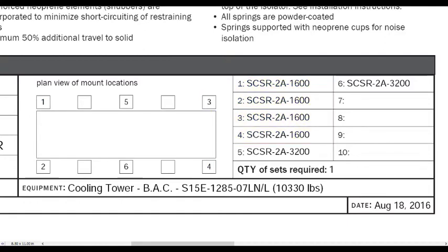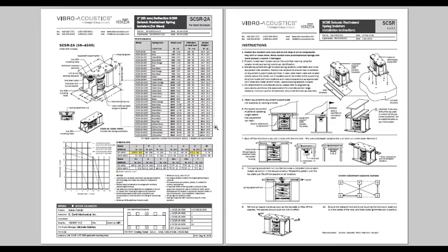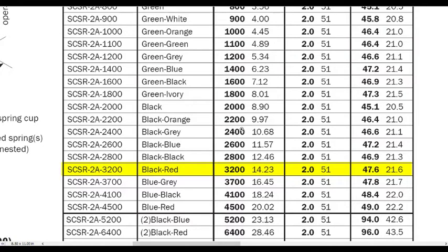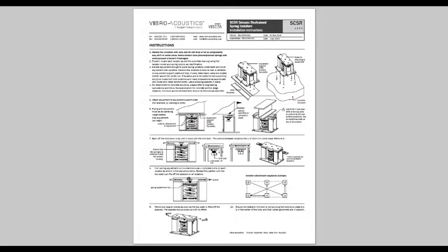When the tower is heavy, or as in this case there are specific support points, it is common to see an additional pair of isolators in the middle, positions 5 and 6. Here we can see that the middle two isolators are SCSR 2A 3200s, and the corners are 1600s. According to the table above, when we check the spring colors at the job site, we should see black outer springs with red inner springs in the middle isolators and green outer springs and black inner springs in the corner isolators. Here is the installation instruction page.